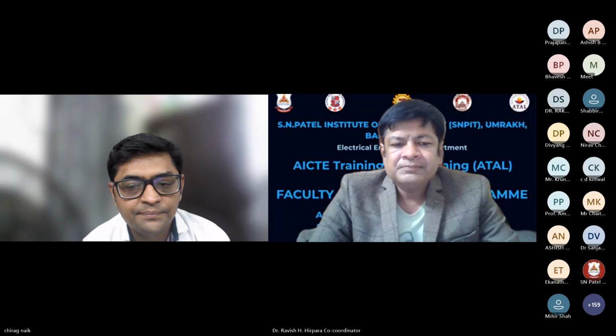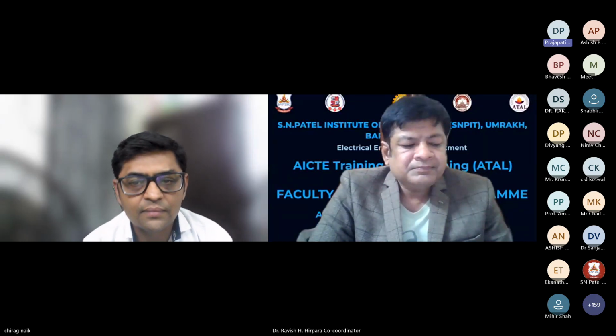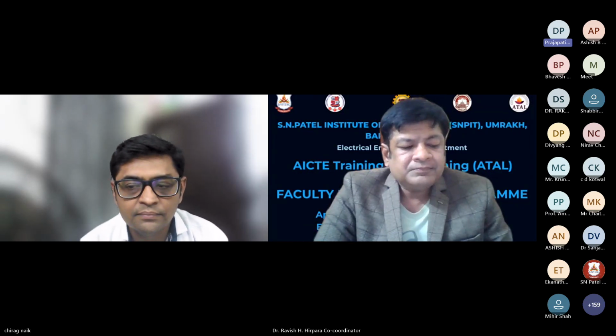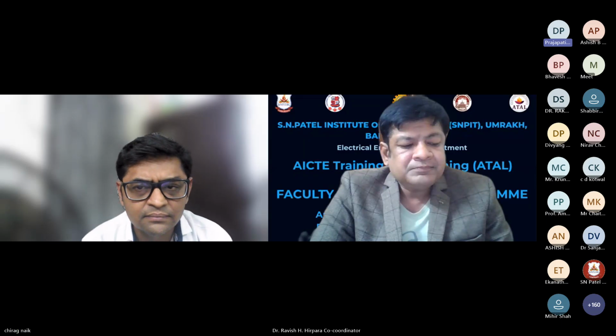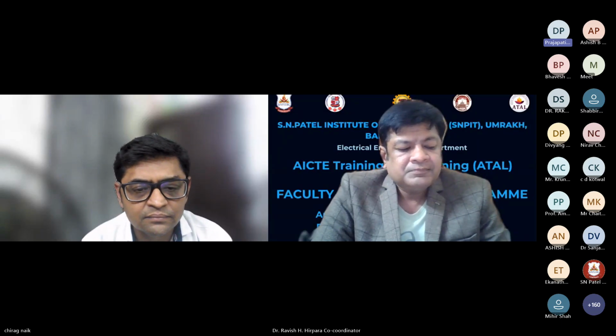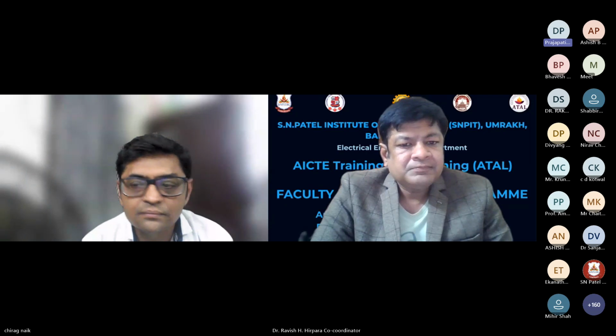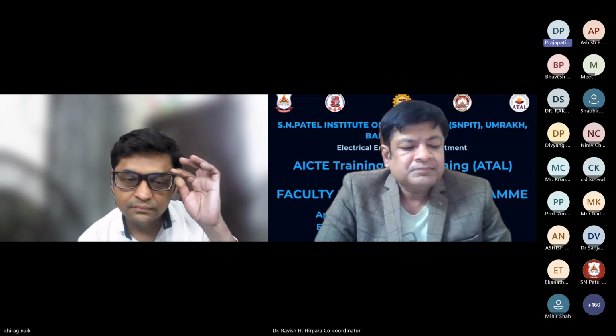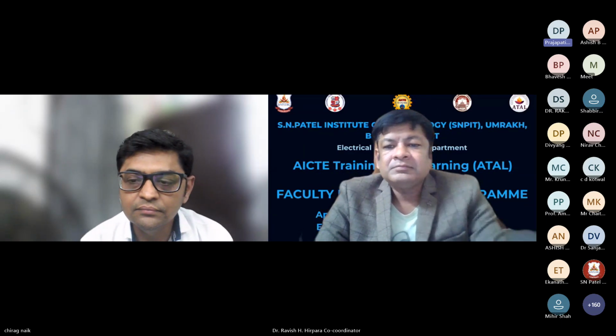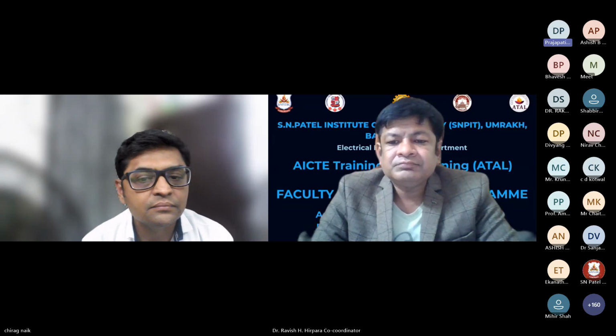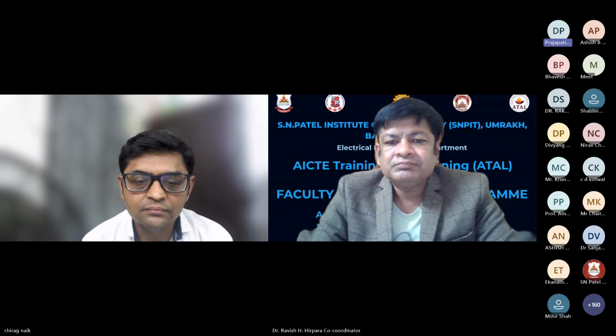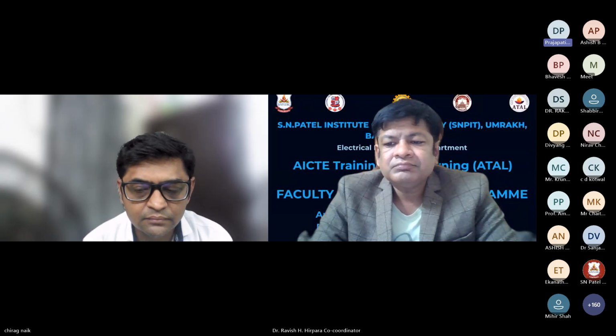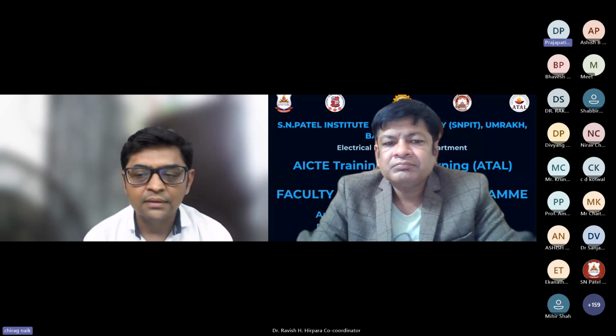The intensity of the transient, and because the arc may reignite or there may be a pre-strike before the contact closes, the presence of arc erodes the contact quality and affects its life. In the field, if the arc persists and is not extinguished in time, there will be extensive electro-thermal pressures on the contact, which can sometimes weld the contacts and make them completely non-functional. So controlling the arc presence and effectively quenching it in the circuit breaker through controlled switching is very helpful. That is how contact life can be reused or prolonged.